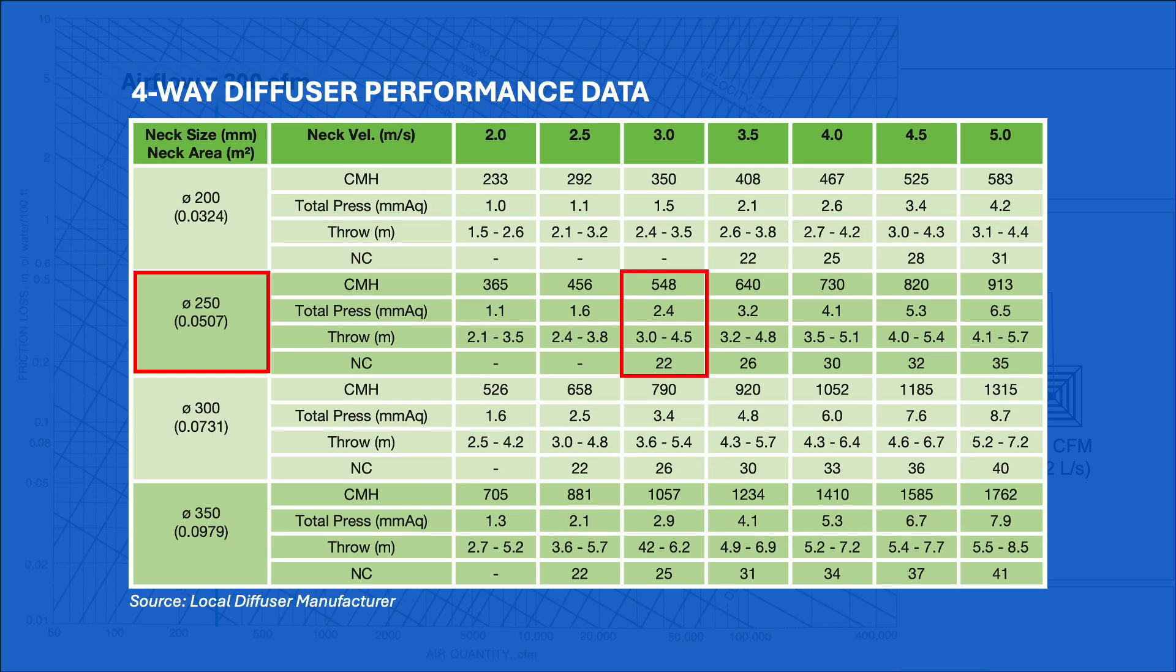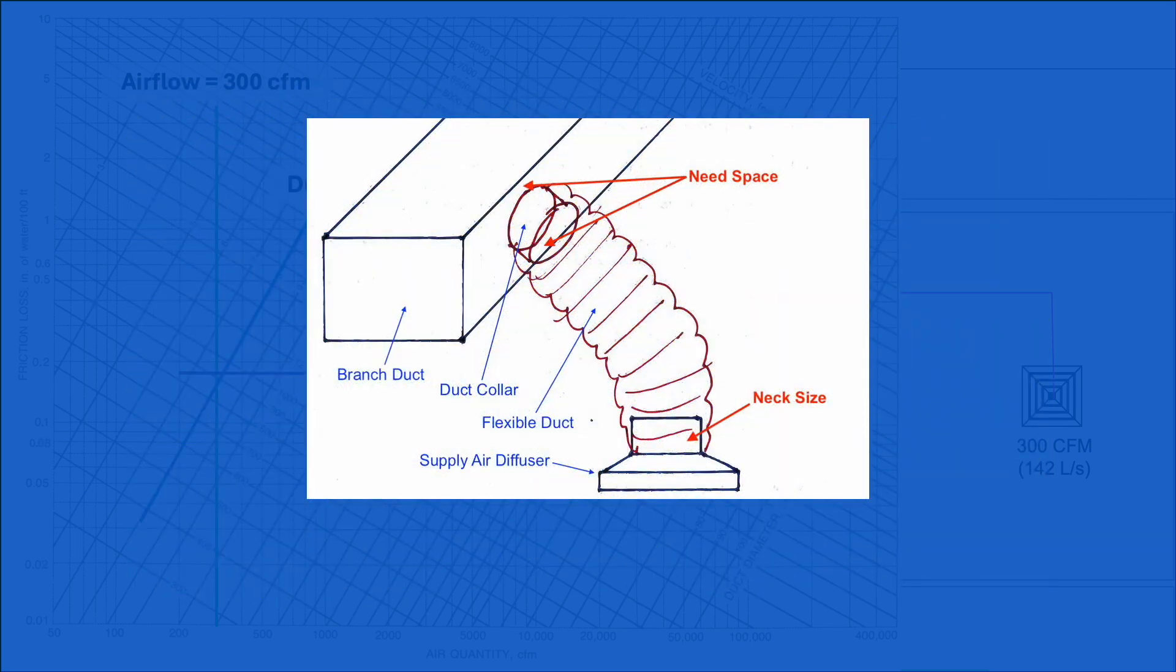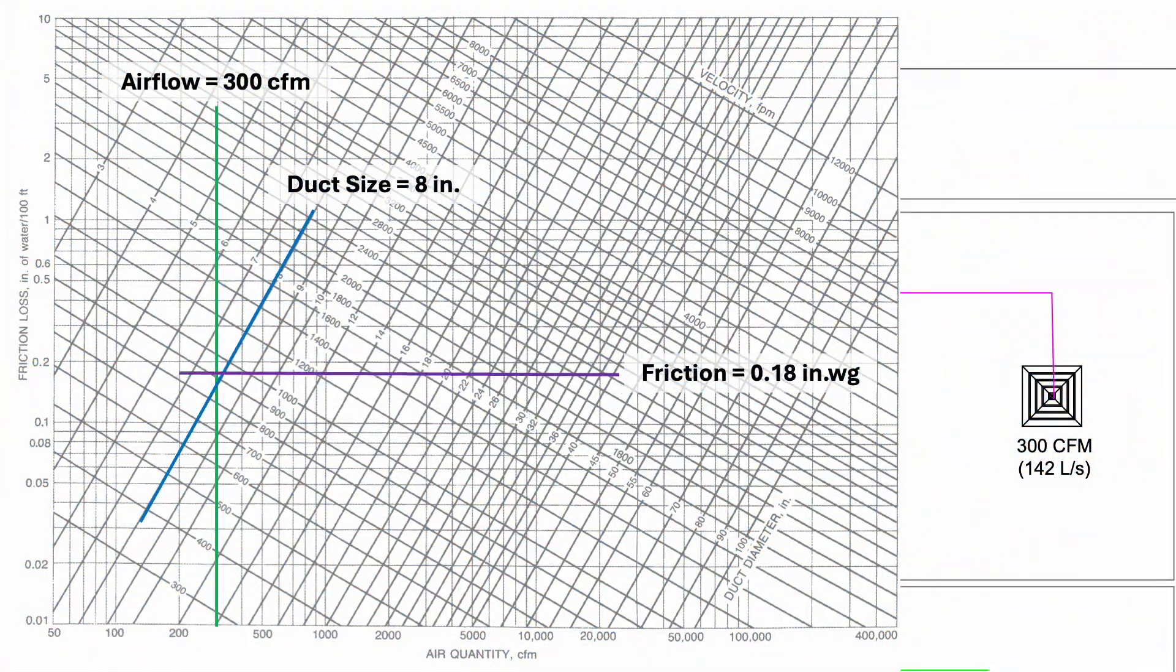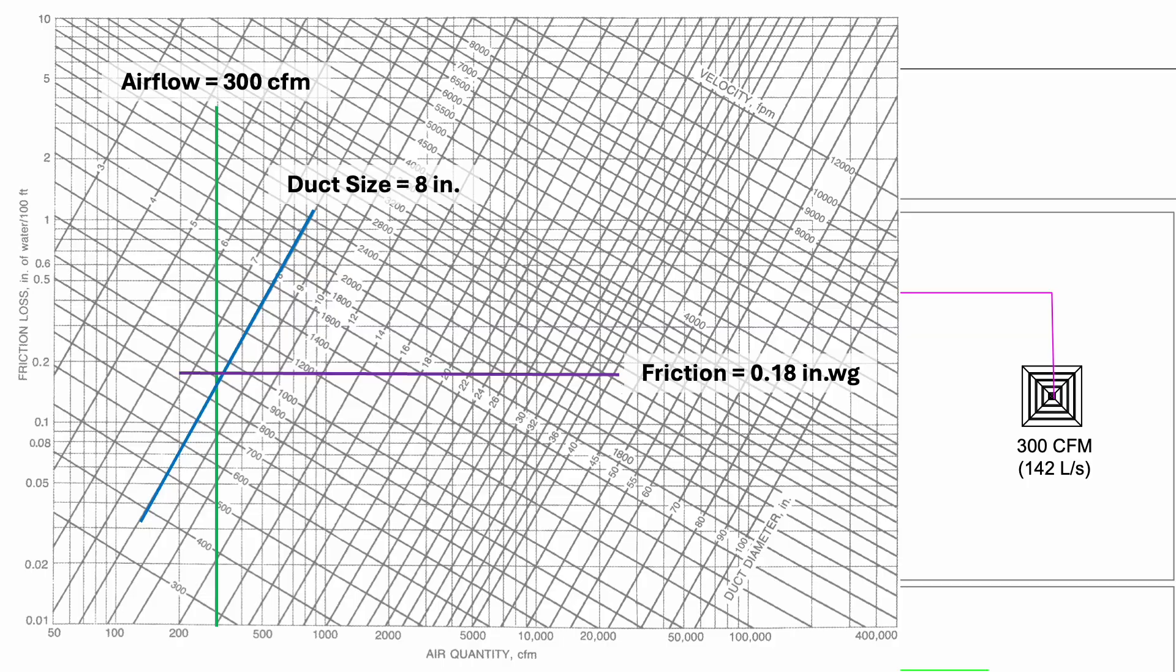However, we need to be careful of the branch duct size as the flexible duct needs space for installation. Generally, the branch duct should be 50 mm or 2 inches more than the flexible duct. Flexible duct can easily get compressed. To account for that, we can use one size bigger than what is shown in the friction loss chart. If the chart shows 8 inches, we use 10 inches.